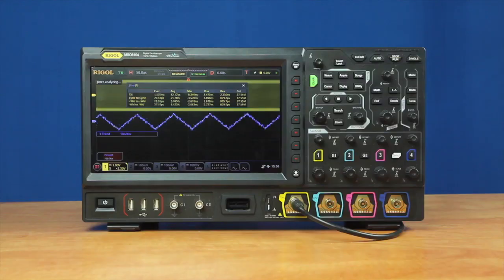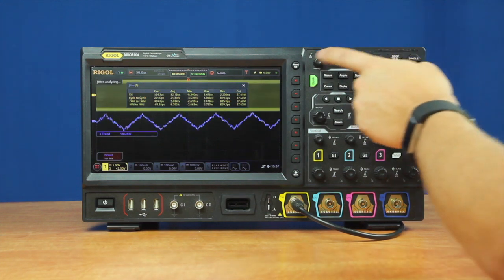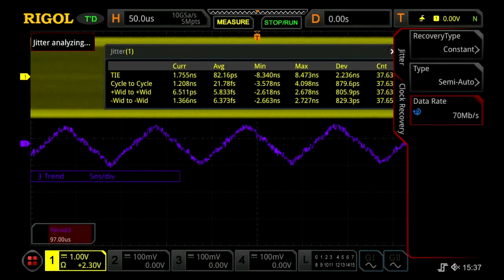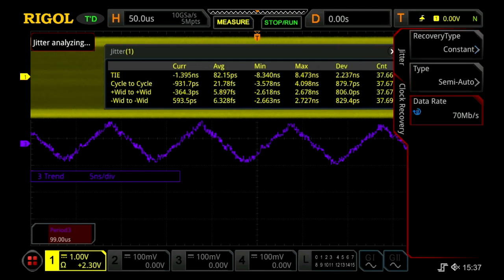One of the advanced capabilities critical to jitter analysis is clock recovery. Depending on the signal type, some receivers will read the clock differently. The MSO8000 can use a constant, explicit, or PLL-based clock recovery.